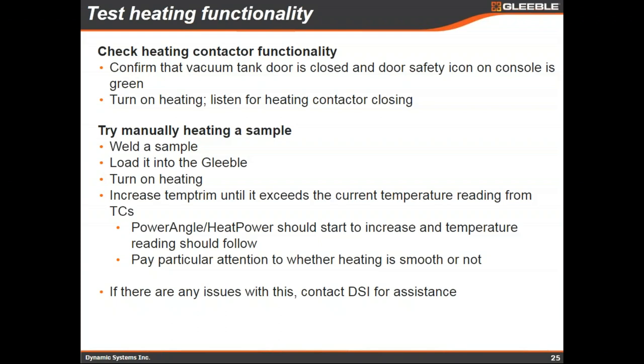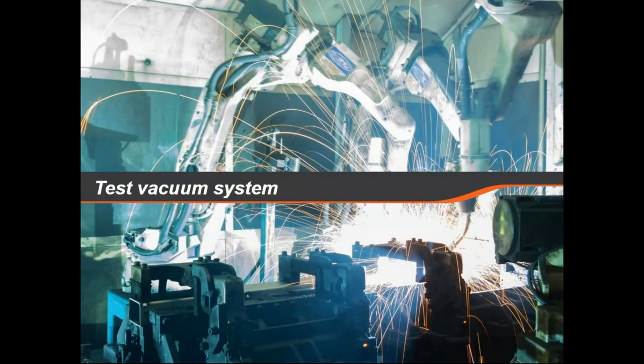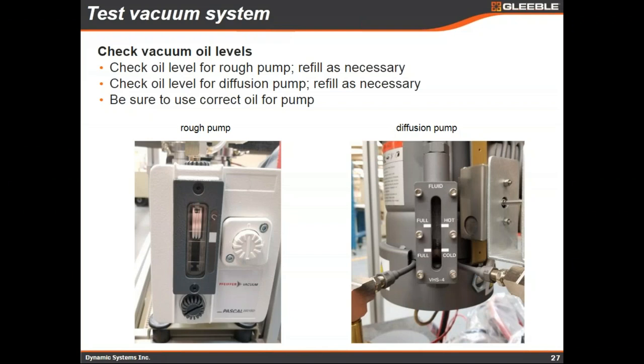If there are heating issues, contact DSI for assistance. Next is the vacuum system, which most users likely have. The first check would be the oil levels in the vacuum pumps. Depending on which components you have, you may have two rough pumps or one, and you may or may not have a diffusion pump. Take a quick look at your vacuum unit and see where the levels lie on any pumps attached to your system.